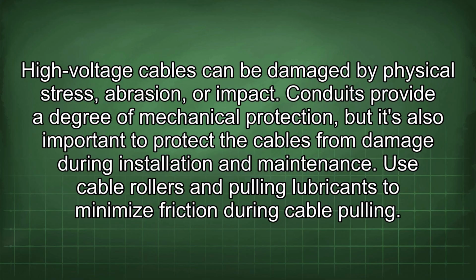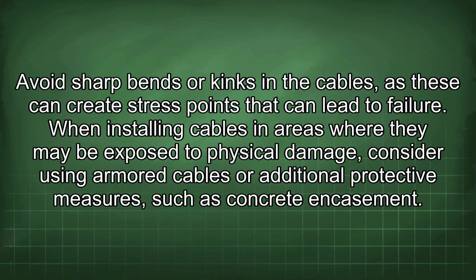Conduits provide a degree of mechanical protection, but it's also important to protect the cables from damage during installation and maintenance. Use cable rollers and pulling lubricants to minimize friction during cable pulling. Avoid sharp bends or kinks in the cables, as these can create stress points that can lead to failure. When installing cables in areas where they may be exposed to physical damage, consider using armored cables or additional protective measures, such as concrete encasement.